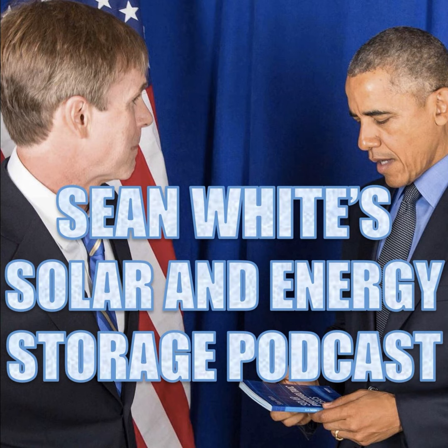690.31(C) Cables: type PV wire or cable and type distributed generation (DG) cable shall be listed. Informational note: UL 4703 is the standard for photovoltaic wire for PV wire, and UL 3003 is the standard for distributed generation cables for DG cable.